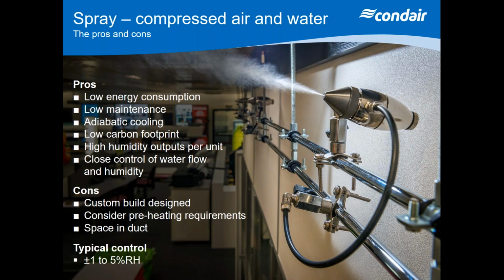So these nozzles are normally mounted at one end of the room, or it could be mounted in an L shape or H shape pattern above the working area. And these are normally going to be mounted in industrial areas where you're looking to spray. You're not concerned too much about noise, because obviously with the compressed air and water system, you're going to see around 70 dBA of noise level. So you can't put this in an office. So these air caps you're going to see on the front of these units will give you a certain capacity, anything from 2.5 litres an hour up to 15 litres an hour. And obviously, if you can imagine 2.5 litres an hour of spray, try and equate that into 2.5 metres of distance of spray pattern off the nozzle.